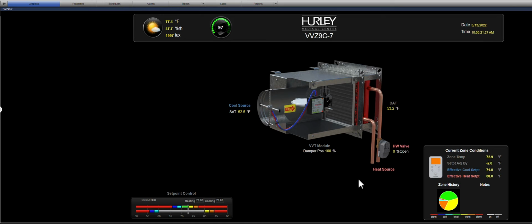So this is where the box is doing its absolute maximum, and it cannot overcome the load in the space. So now we have to evaluate, is this box too small for what that space is now? Do we need to resize it to bring in more fresh air, more cooling air? We can go down and do a balance and find out if it's been limited against its base design. It probably is fine. It probably puts out the CFM that it was supposed to.